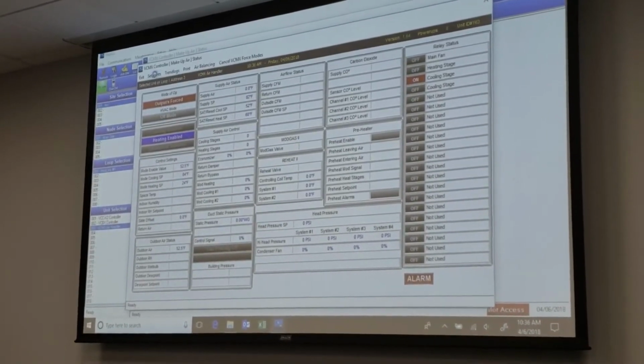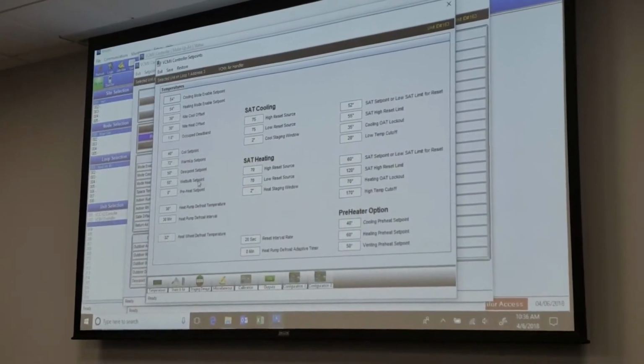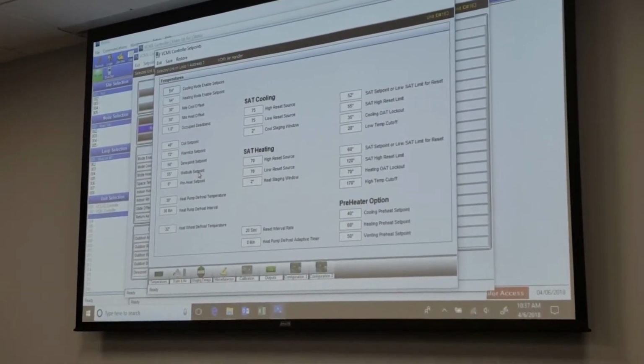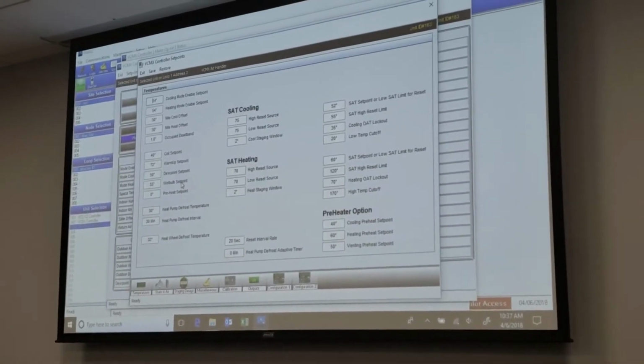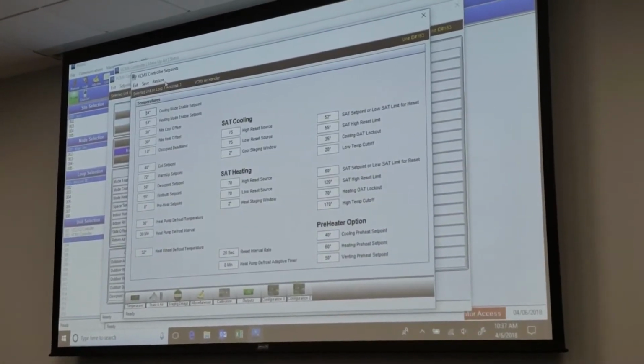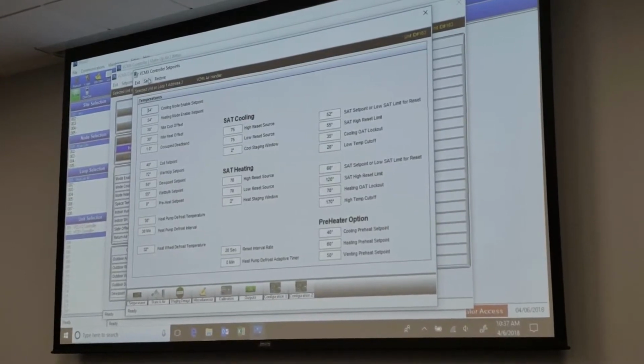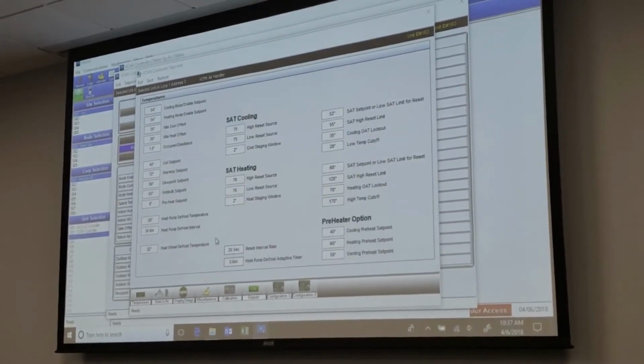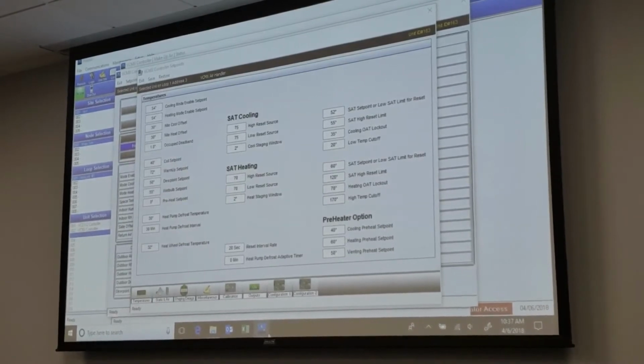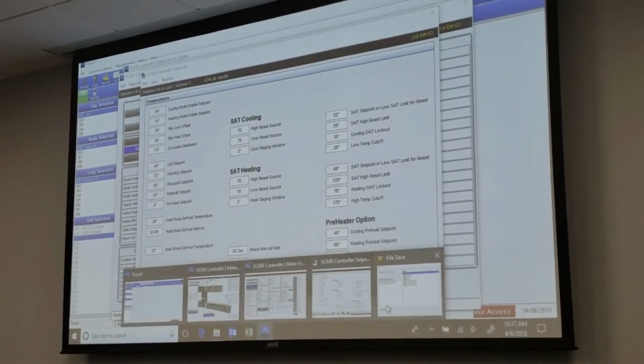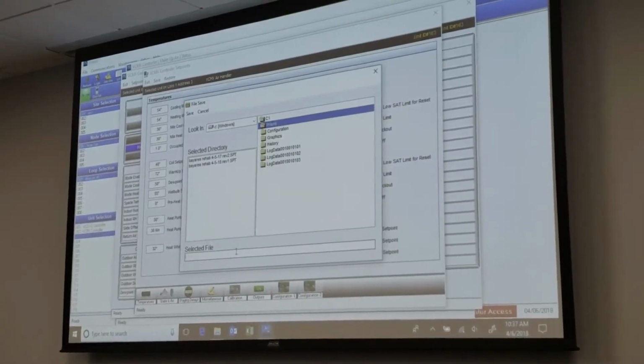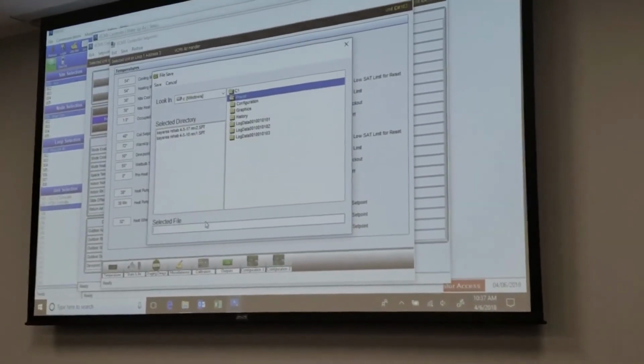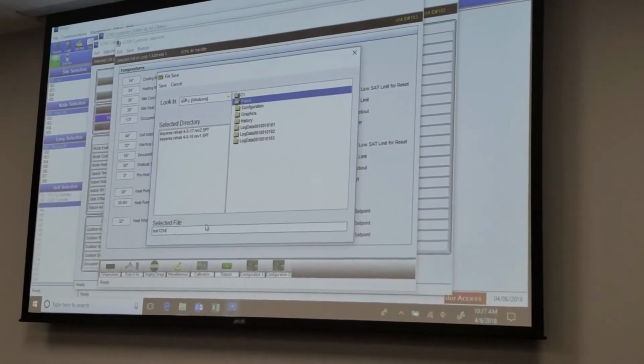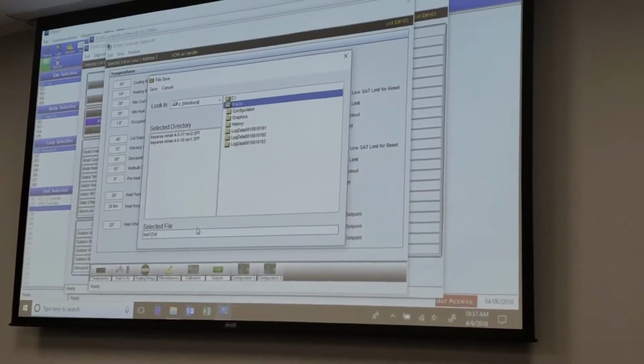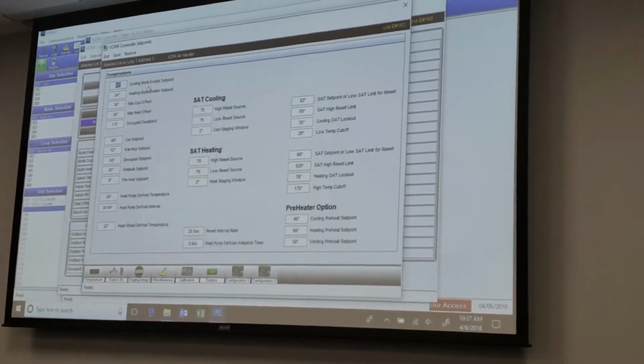I can actually go to set points. There's all my set points. If y'all do use Prism Software, one of the things that I recommend y'all doing when y'all first walk up to a unit, plug into it, discover it, get to this point, and hit Save Set Point. Save, and it just disappeared. So, get to this point, and that screen pops up, and I can go name it, whatever job site, RTU, whatever, and then just hit save.